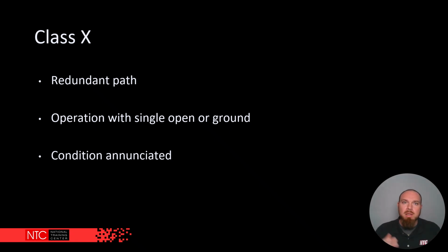You have a little bit more of this redundancy so that the circuit will still operate. Your condition is still going to be annunciated back at the panel. It'll come in as a trouble, but the circuit will still continue to function even with that open or even with a ground fault to it.